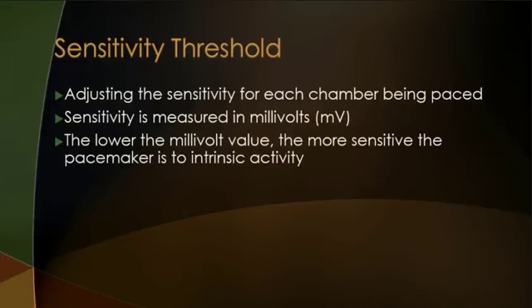So sensitivity threshold, this is adjusting the sensitivity for each chamber being paced. Sensitivity is usually measured in millivolts. The lower the millivolt value, the more sensitive the pacemaker is to intrinsic or native or the patient's own cardiac rhythm.